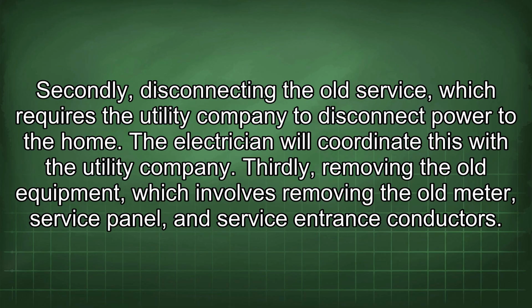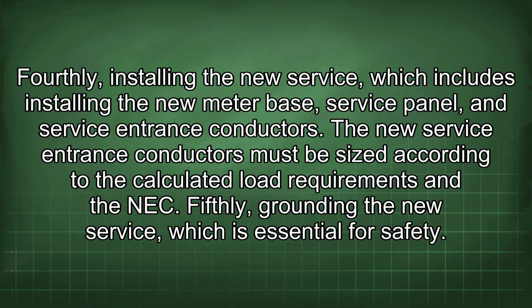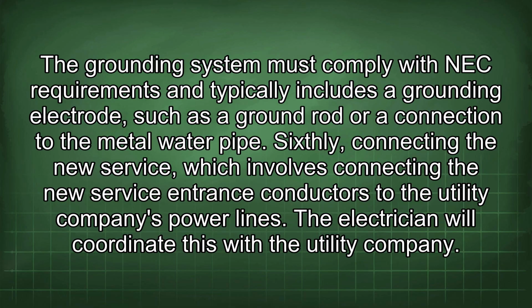Secondly, disconnecting the old service, which requires the utility company to disconnect power to the home. The electrician will coordinate this with the utility company. Thirdly, removing the old equipment, which involves removing the old meter, service panel, and service entrance conductors. Fourthly, installing the new service, which includes installing the new meter base, service panel, and service entrance conductors. The new service entrance conductors must be sized according to the calculated load requirements and the NEC. Fifthly, grounding the new service, which is essential for safety. The grounding system must comply with NEC requirements and typically includes a grounding electrode, such as a ground rod or a connection to the metal water pipe.